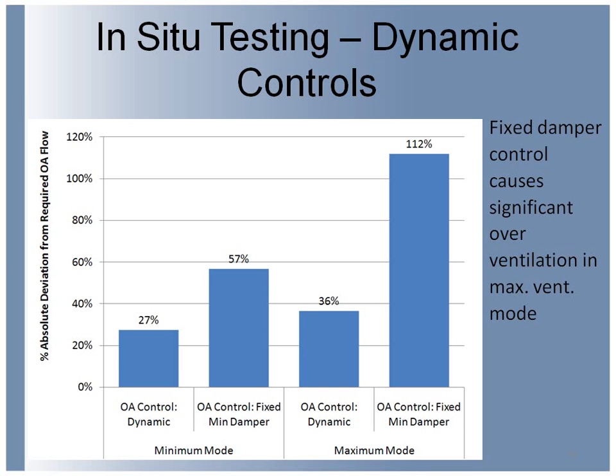And that is, if you look at the difference between minimum and maximum modes of these variable volume systems, so kind of nominally heating to cooling, if you want to think about it that way, you see a huge difference in those systems that don't have the dynamic controls, which is what we would expect, but I think really important outcome. So for the dynamic control systems, we see a relatively slight increase as we move from the minimum flow, total flow, to the maximum total flow, because the dynamic controls are nominally doing what they should be doing to control that amount, that ventilation rate. But if you look at those with the fixed minimum damper positions, again, the predominant system that we see in the field, it's doubling as we go from minimum to maximum, and we know that maximum is happening at our peak cooling time in the summer, when we definitely don't want to be bringing in 100% more outside air than we need to be bringing in.